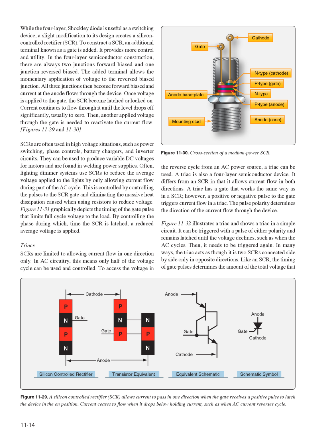Figure 11.31 graphically depicts the timing of the gate pulse that limits full cycle voltage to the load. By controlling the phase during which time the SCR is latched, a reduced average voltage is applied.